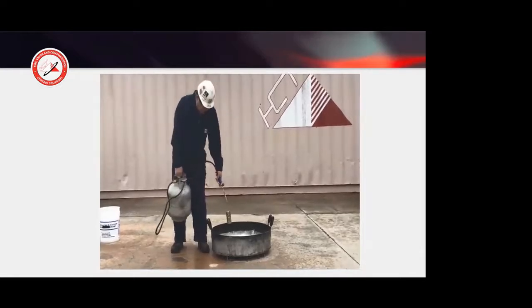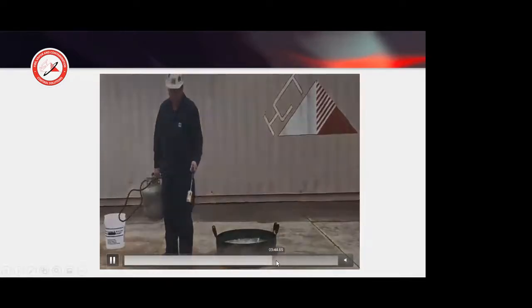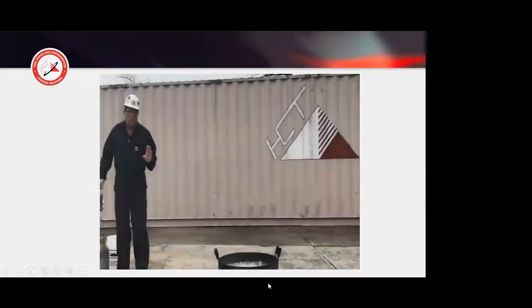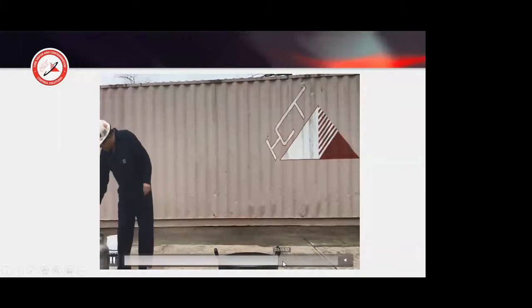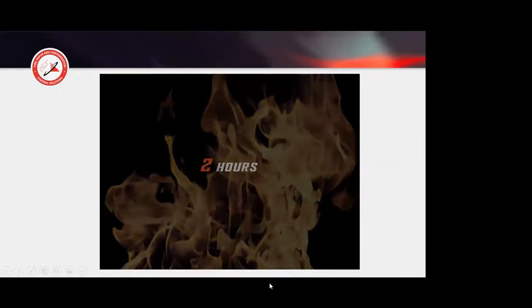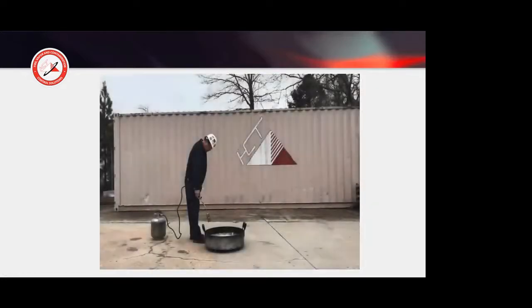But this test also has a burn back resistance test 2 hours later. Hope I didn't miss that mark. So we're going to let it sit, and then we come back 2 hours later and apply the torch. Well, again, the plain water and wetting agent failed the 1 minute. At this point, the foam blanket is totally dissipated, and this would light off like a Roman candle. And here you can see the encapsulator agent. I'm taking my torch and throwing extra flame in there, and you can see it's still not lighting.